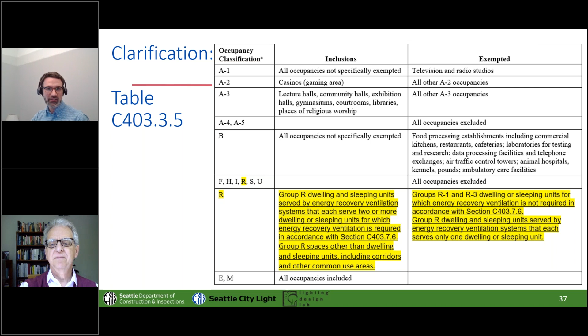Yeah, let me say a thing about residential for a second. My energy-saving heart feels a little stab every time I get up on the roof and there's a 100% outside air unit without energy recovery in a residential building. It's very common to just pressurize the corridors. It's a slightly larger unit and a second return duct, and I can show you energy model after energy model where that has a 7 to 10 year payback, and that is actually borne by the building owner. So it's just good money to do, even if you have a way around it by not making any central units and so on.